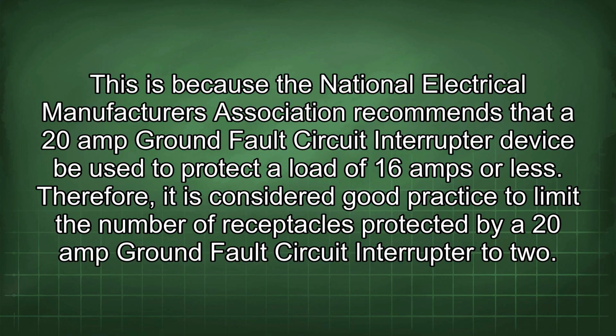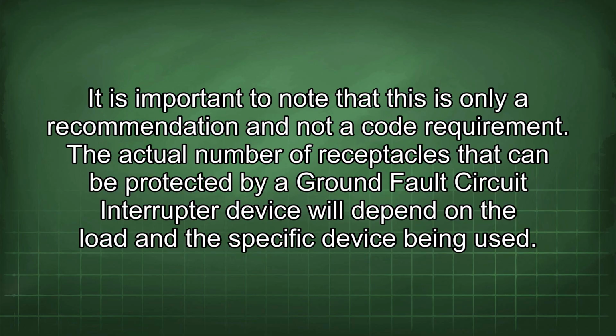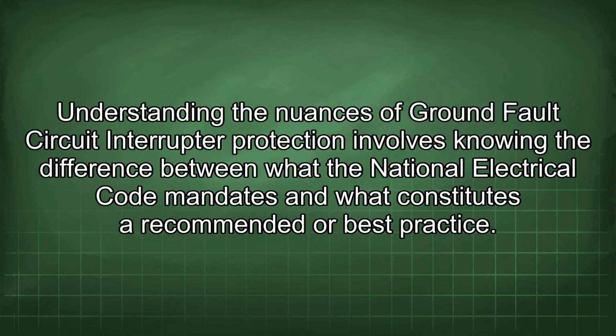Therefore, it is considered good practice to limit the number of receptacles protected by a 20-amp ground fault circuit interrupter to 2. It is important to note that this is only a recommendation and not a code requirement. The actual number of receptacles that can be protected by a ground fault circuit interrupter device will depend on the load and the specific device being used. Understanding the nuances of ground fault circuit interrupter protection involves knowing the difference between what the National Electrical Code mandates and what constitutes a recommended or best practice.